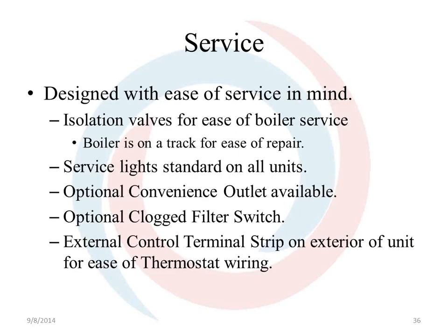A little bit about service. The unit was designed with ease of service in mind. There's isolation valves on all the boilers, and the boiler is on a track for easy pull-out to repair the unit, whether it's on the roof or inside. Service lights are standard on all units, so no having flashlights and looking for a magnetic side to put your flashlight on to light up, look at different things when you're repairing things. Optional convenient outlets are available. Again, you could use that for the heat trace. You have an optional clogged filter switch, and the external control terminal strip is on the outside of the unit for ease of thermostat wiring.